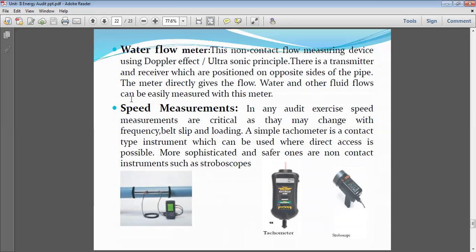Water flow meters are also necessary. In the utility section, we must measure water input and how much water is utilized in different processes. If water wastage is high, we need to do water conservation. Conserving water means lifting smaller quantities — effectively reducing pumping needs. When the quantity of water pumped is reduced, the energy used to run the pump also reduces. So water conservation ultimately leads to energy conservation.